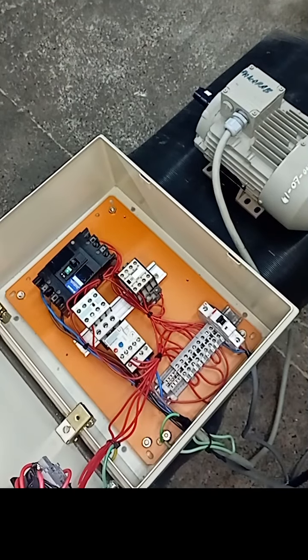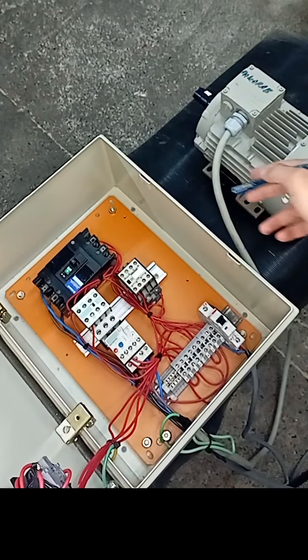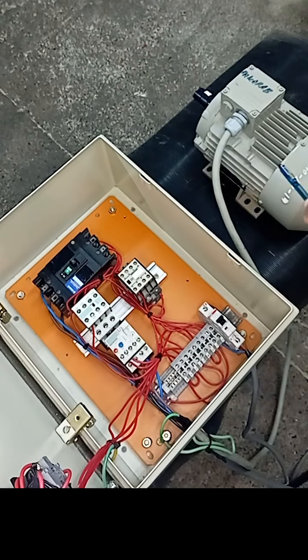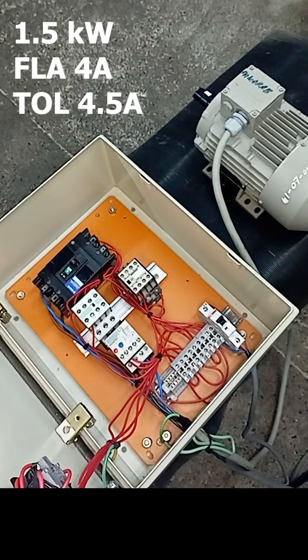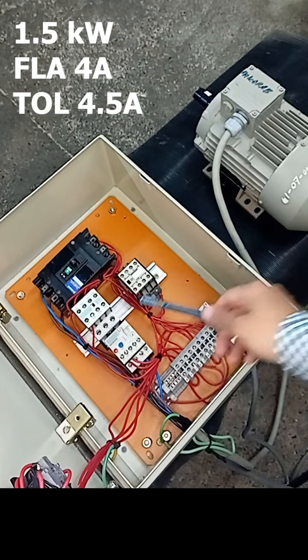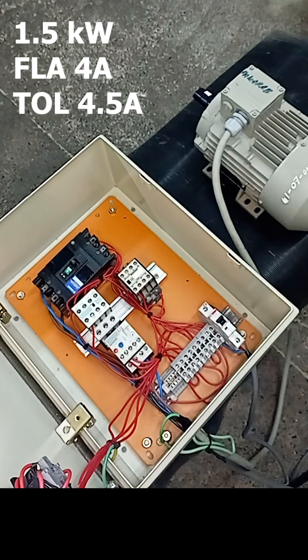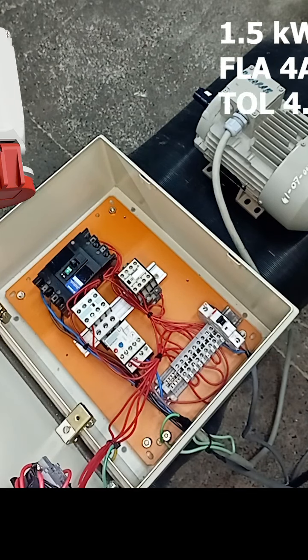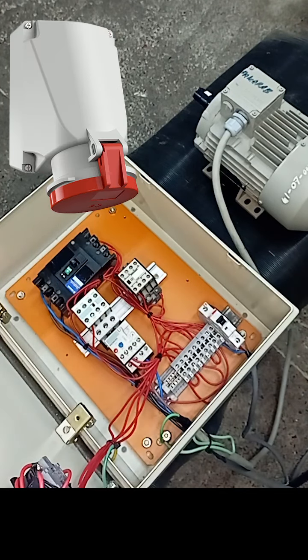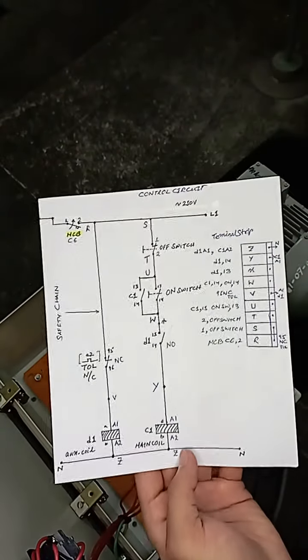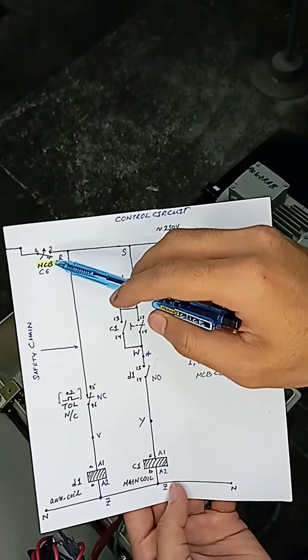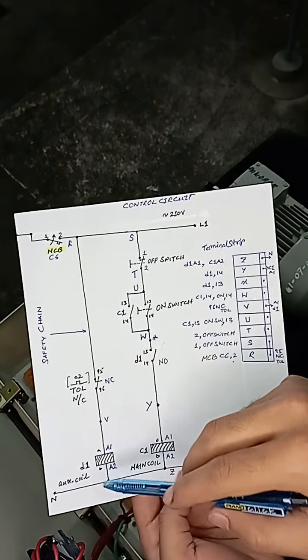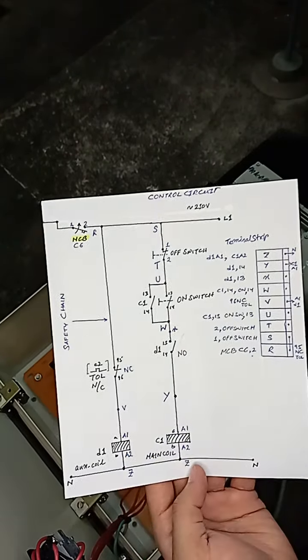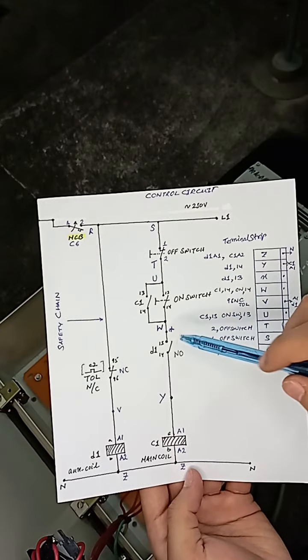The direct online circuit has been set up to test its operation, and for that a three-phase induction motor has been connected to it. This is a 1.5 kilowatt motor that consumes about 4 amperes at full load. Hence the thermal overload relay has been set to 4.5 amperes and the circuit is being supplied by three-phase power from an industrial socket. According to the single line diagram, closing the circuit breaker C6 allows the current to flow through and energize the auxiliary coil D1. And once D1 is energized, the normally open contact of D1 would close and now the motor can be started with the push of the on button.